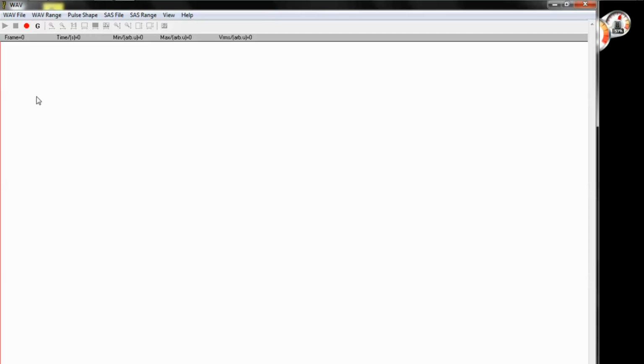Now we're going to change the voltage on the unit, and I'm going to set it to 850 volts, which is within the operating limits of my detector. I would warn you to be very careful about the actual voltage that you supply to your detector. You need to read your manual. If your detector only goes to 850 volts, don't go over 850 volts. Typically, the detector can take the additional voltage, but doing so is going to greatly reduce the length of its life. And do you really want to buy a new detector soon? I know I don't. So be really careful with your detector.